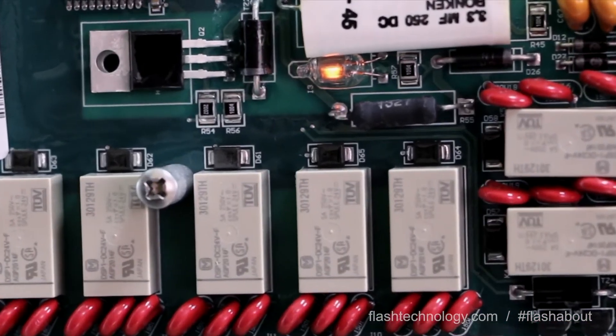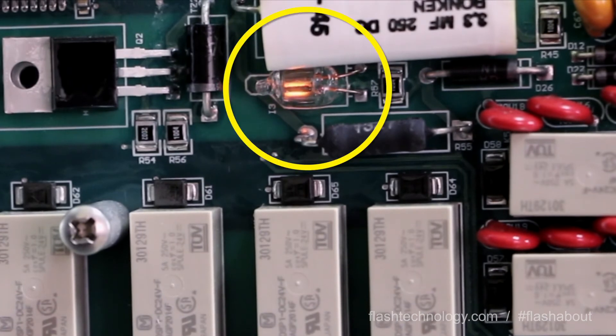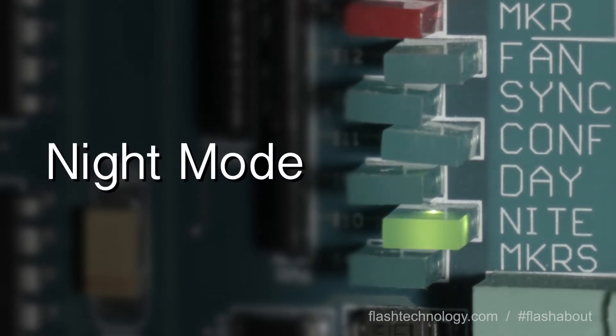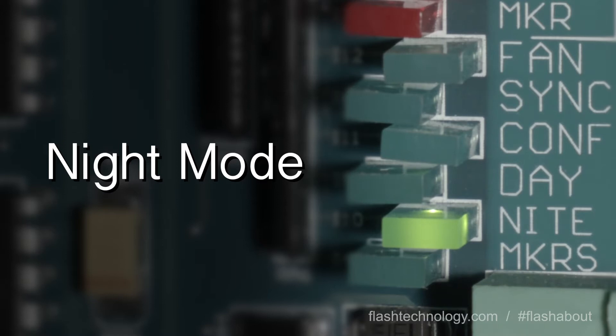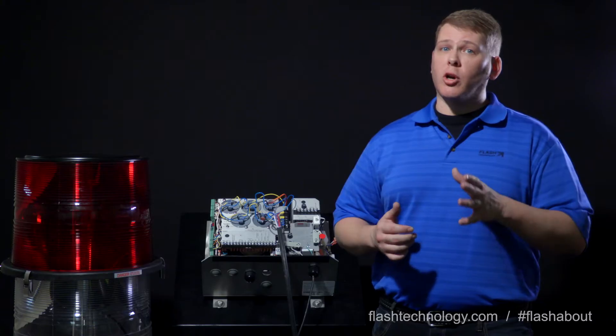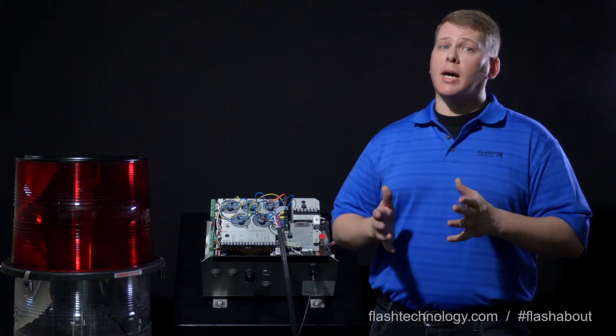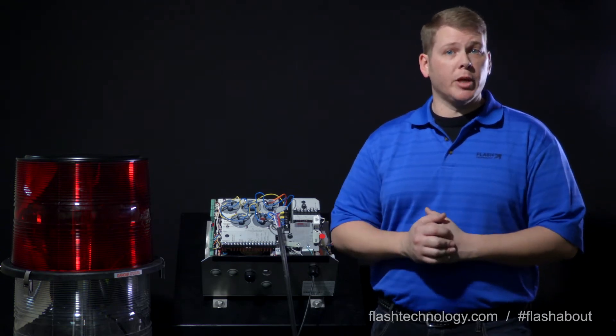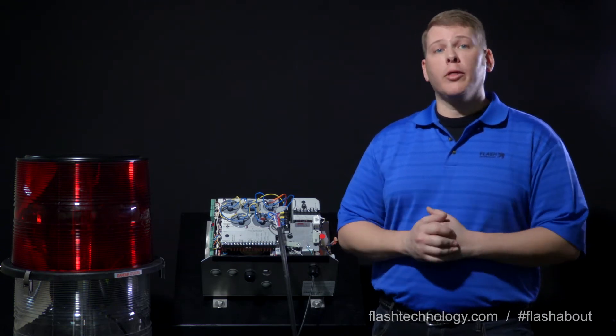If the neon is lit, the trigger voltage is likely present. Also, there should be an audible ticking noise in day mode and a buzzing noise in night mode. If you do not hear this audible tone or the neon is not lit, we need to verify trigger voltage is being supplied to the timing and trigger board and or the trigger transformer.